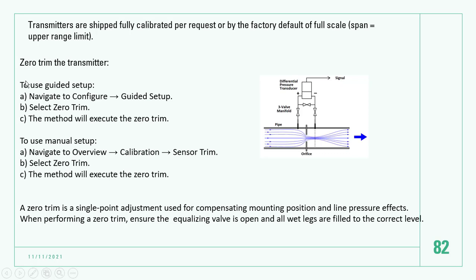You can use two kinds of setup: use the guided setup like this, select zero trim, execute zero trim, or use manual setup. In the Delta V DCS system, you can set up everything. Before you set up, you should do this job on the site. Okay, or if you don't know how to do it, you can disconnect here, make sure both sides are open to the atmosphere. It's the same pressure. 14.7 is the PSI of the atmosphere. Okay.